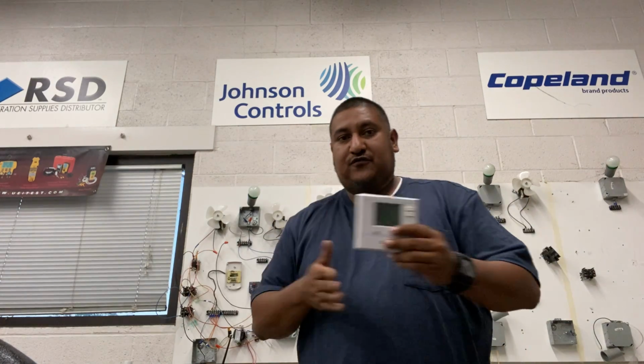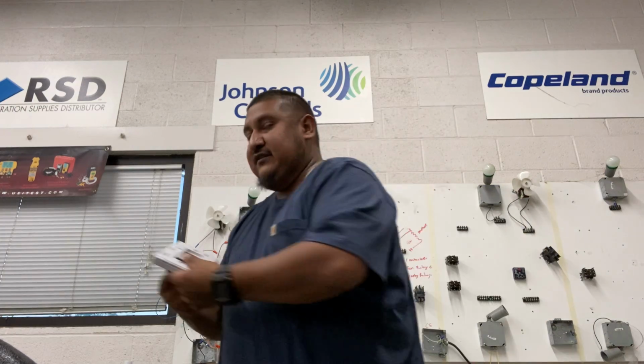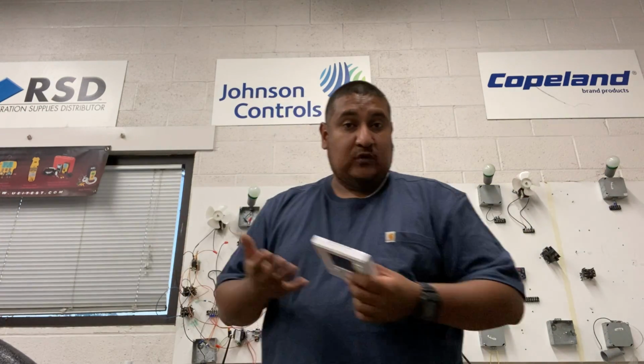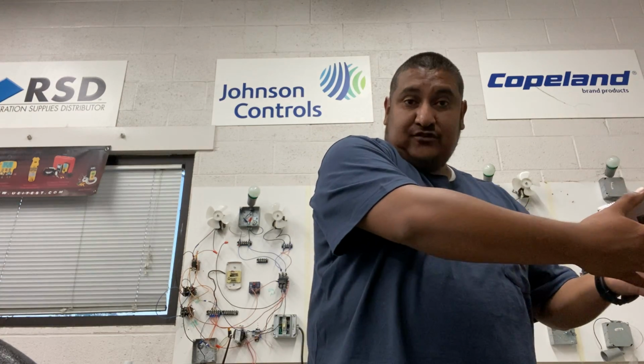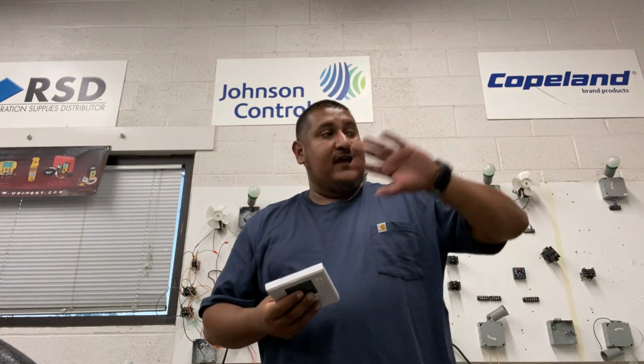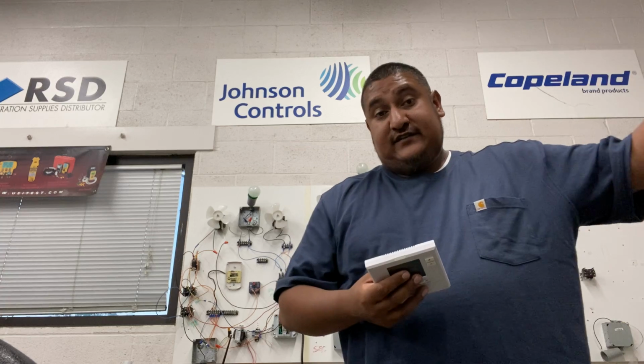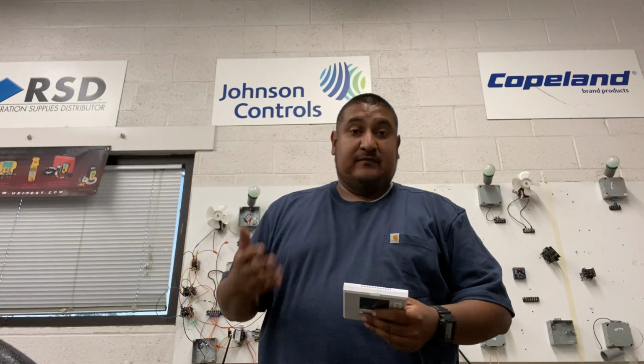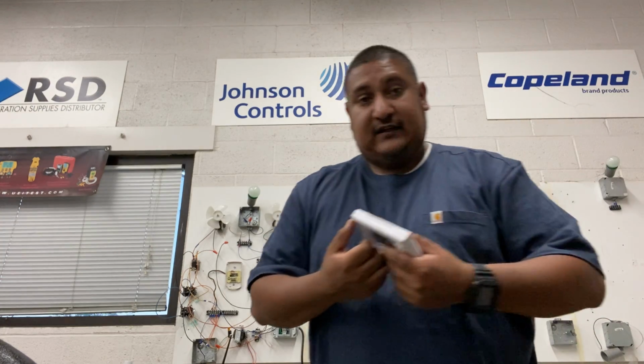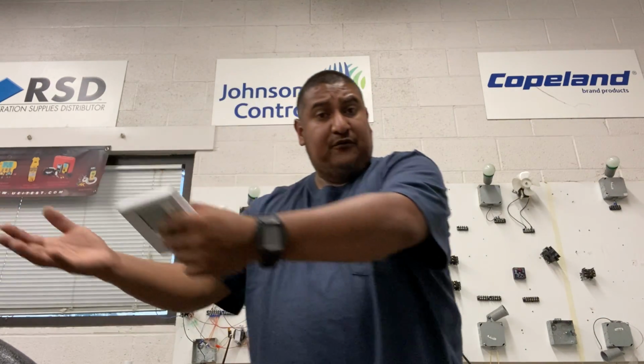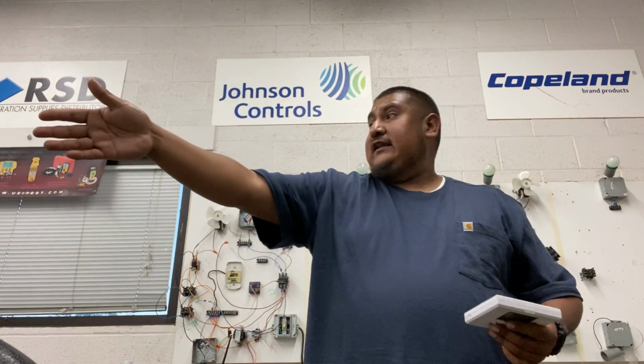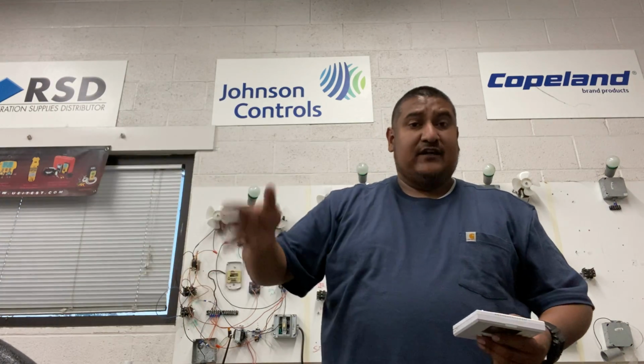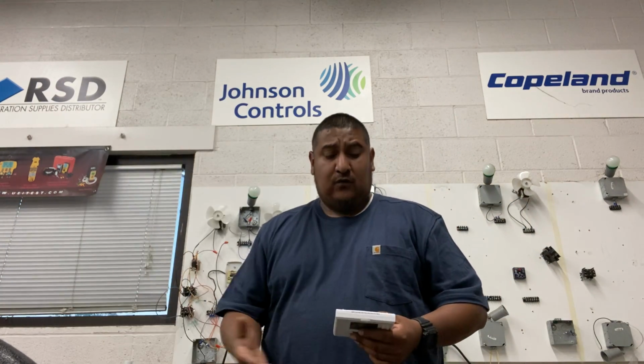It's switching those 24 volts. It takes those 24 volts and gives them to the yellow for cooling, or it'll give them to the white, the heating circuit, telling everything on that circuit to activate. And the green, which is for our fan, takes those 24 volts so any relay hooked up to the green wire goes ahead and activates. That's the way it works.